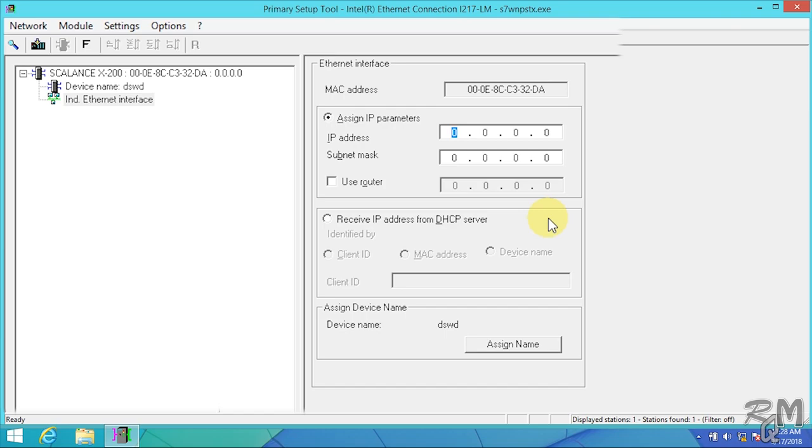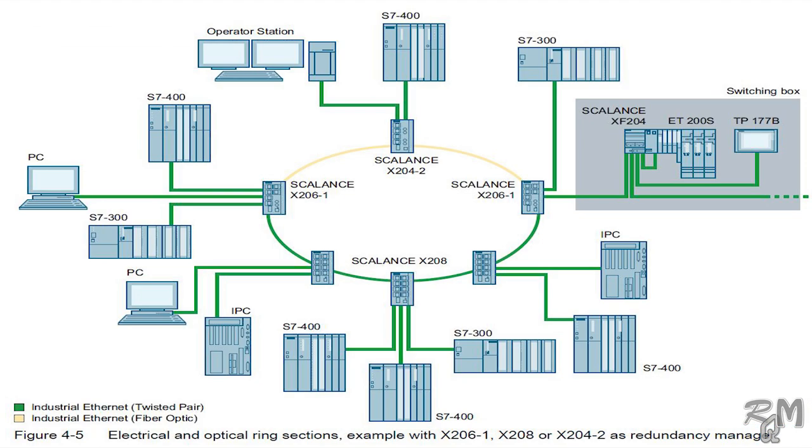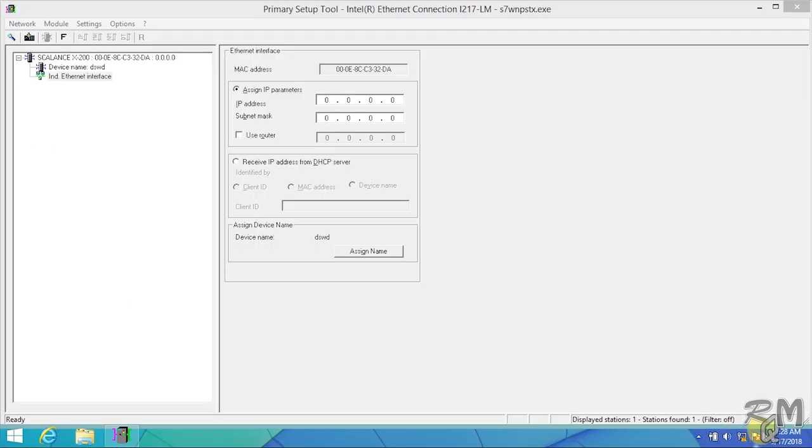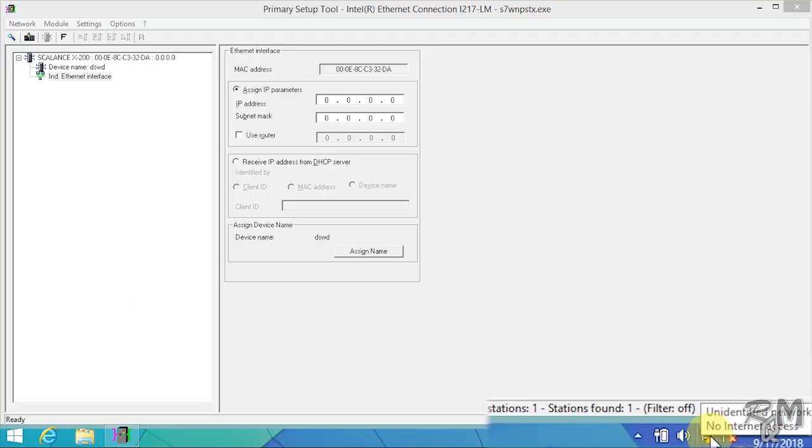If you click on SCALANCE X200 it will expand and you can see general information on right side window. Second row is showing device name and if you click on third row of industrial ethernet interface, here you will get options to assign IP address and name. If you have connected new SCALANCE switch directly to your plant network, then you can assign IP address and subnet mask according to your SCADA or DCS architecture drawing. By using your engineering station it is possible but I will not recommend it, especially in case of plant bus which is responsible for communication of PLCs. There will be small risk of tripping.